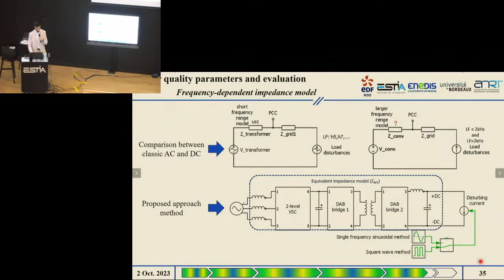Our proposition to address this was to use either the model of the power electronic converter or the real converter prototype, and connect in cascade at the output a source of current disturbances with different shapes, such as sinusoidal shapes for frequency scanning methods with higher precision, or squared or pulsed waves for a broader frequency-dependent model using only one experimental test.